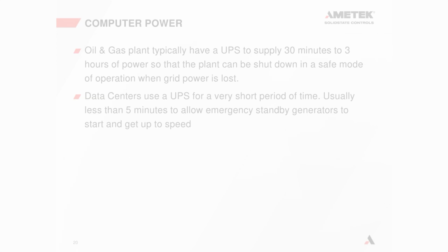And then only after the emergency standby generator says, right, I am good, will an automatic transfer switch in the system transfer over to the emergency standby generators, and all of the power will transfer from the UPS to the standby generator until the grid power comes back on.